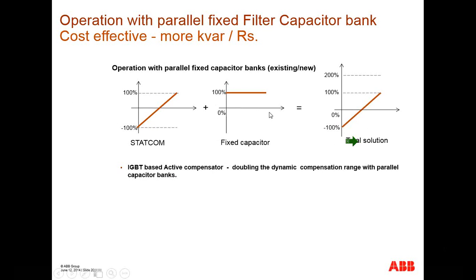Most of the electricity utilities already have some fixed compensation, as I explained. Conventionally, they use that fixed switched capacitor. So if we combine it with the STATCOM, then you can look here. Once it is combined, it goes from plus 100 to minus 100. So it means it is from 0 to 200, and the capacitor never has to be switched on and off. Without that, it can keep directly from 0 to 200%. So just by adding one solution into the existing system, it can be upgraded to a variable 0 to 200%.